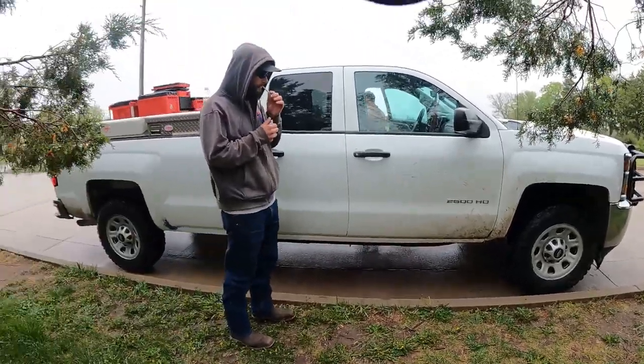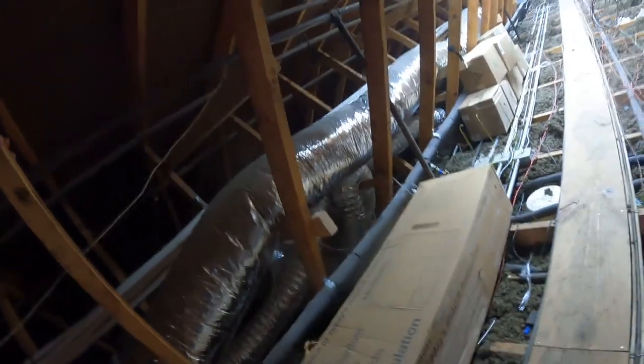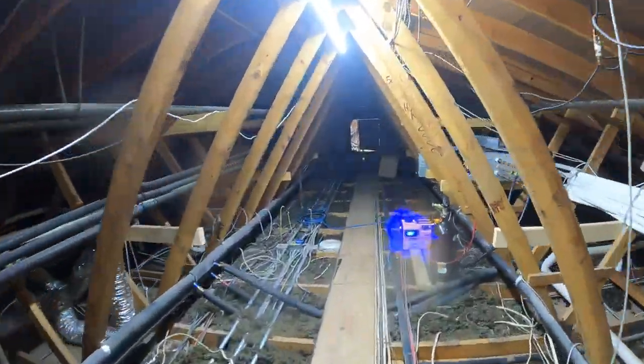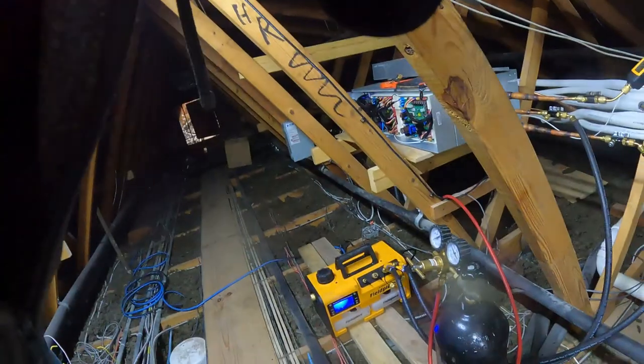I think dad went mudding in the new truck. We're back to check on this vacuum and I can hear it already, so I'll show you guys. Dad already looked at it from his phone because his tool is so cool — we can do that — and it shows 29 microns, it shows 30, and it's loud.